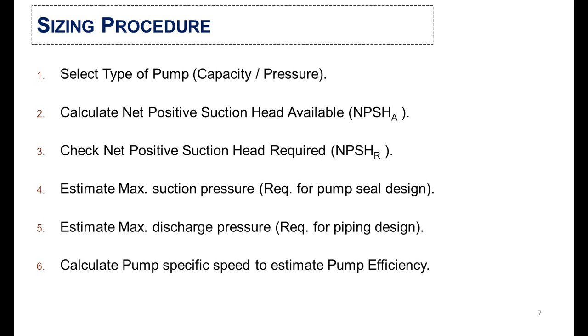In the third step, you will verify the net positive suction head available against the net positive suction head required — this is the critical part of pump sizing. In the fourth step, you will estimate the maximum suction pressure for pump seal design. In the fifth step, you will estimate the maximum discharge pressure for downstream equipment and piping design. In the last step, you will calculate the pump specific speed to estimate the pump efficiency.